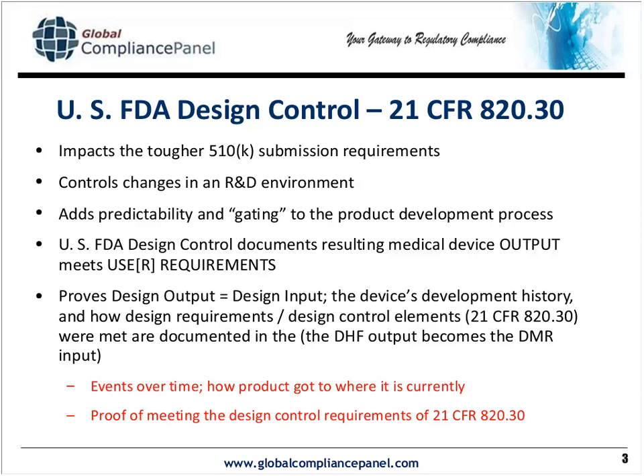Now, as I mentioned, the United States Food and Drug Administration design control requirements are formulated in 21 CFR 820.30. This is since 1996-97. That's the time the FDA added this requirement to the GMPs for devices, and they gave industry about a year to come into compliance to it.